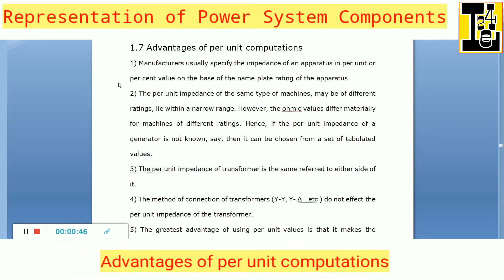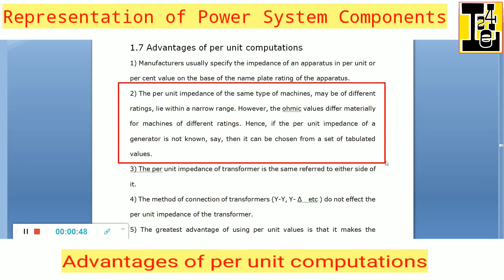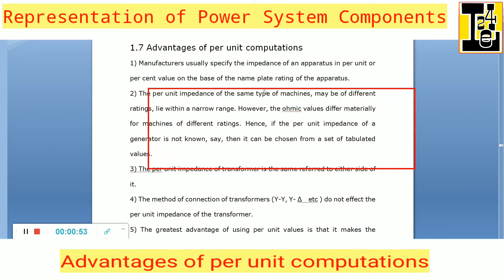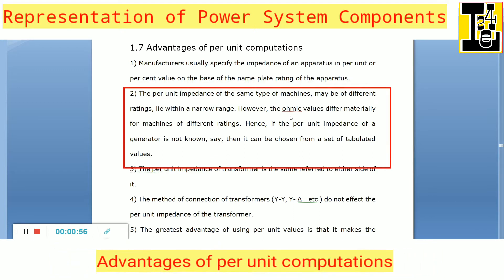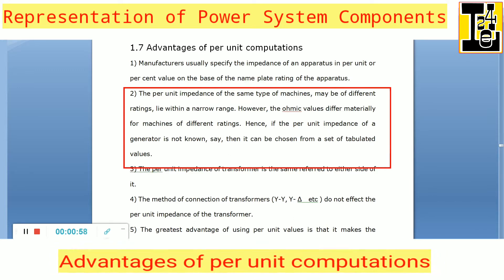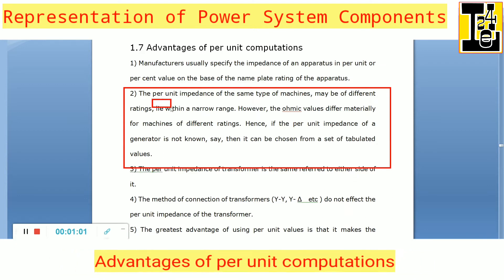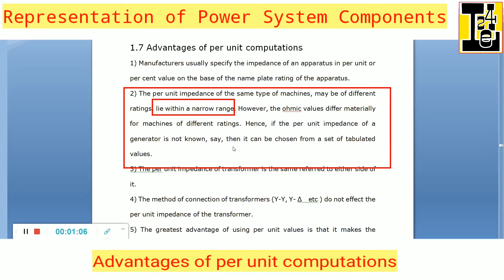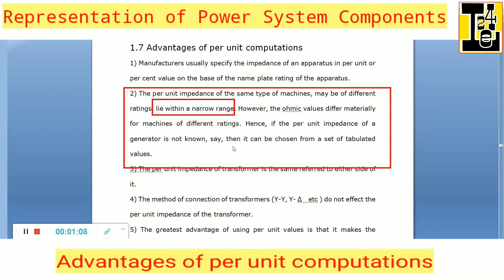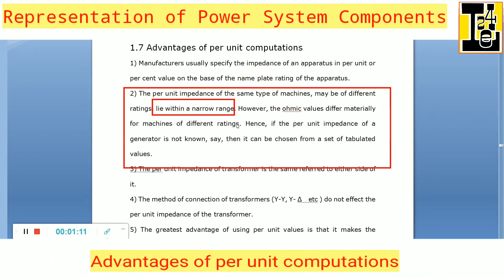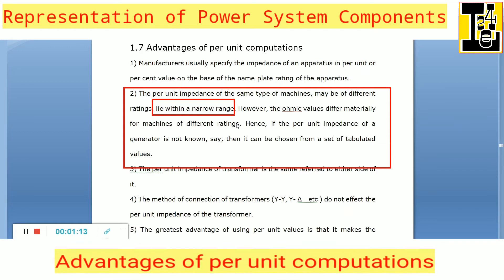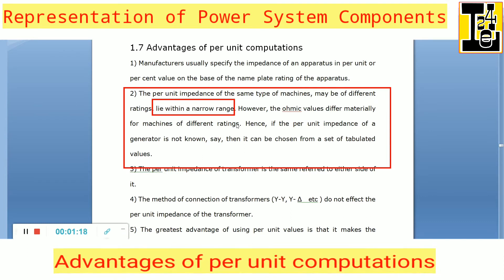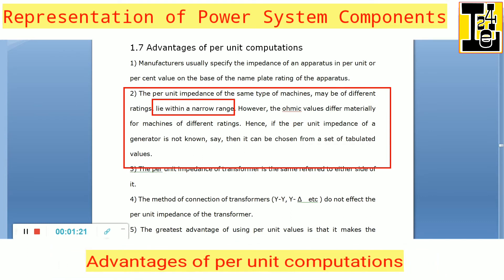The second advantage of per unit computation is that the per unit impedance of same type of machines of different ratings lies within a narrow range, however the ohmic values differ materially for machines of different ratings. Hence, if the per unit impedance of a generator is not known, it can be chosen from a set of tabulated values.